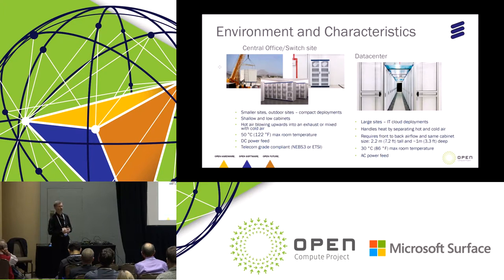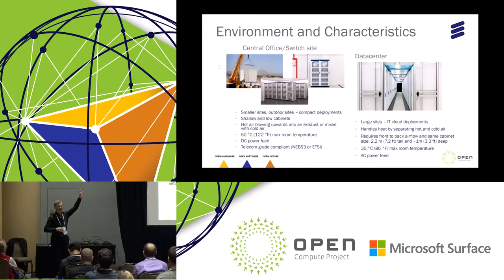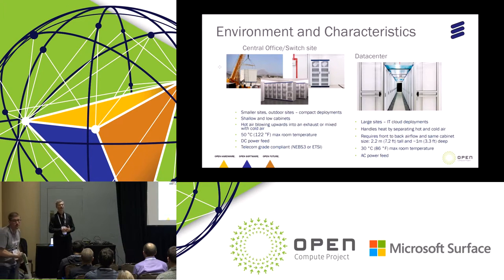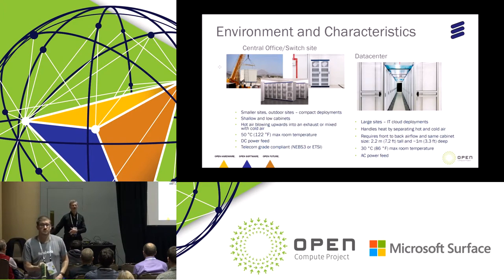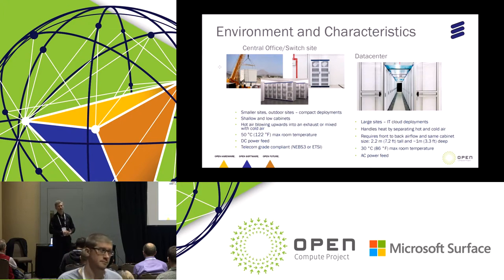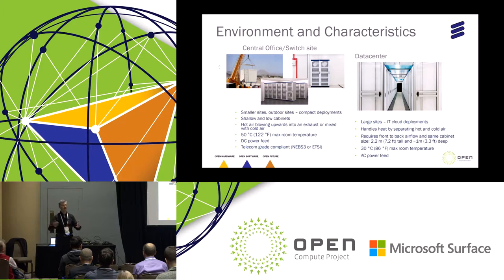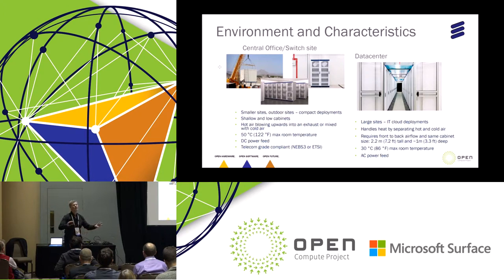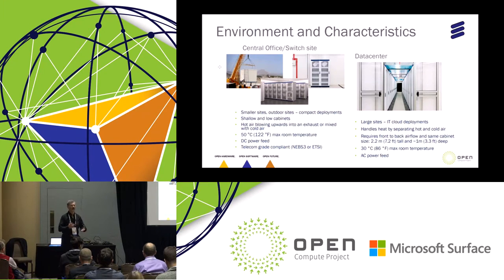This is a very normal type of environment for what we in the telco world call central office environments — shallow type of equipment, normal air, blowing it so there's maybe a vent at the top. DC power feed is very common; many of these existing installations have a minus 48 volt battery pack. It's a very expensive installation — you don't throw out the battery easily and replace it with 230 volt AC and UPSs. It's expensive replacement because it's not one, two, or three — it's thousands of them. And there are also things like vibration to deal with.